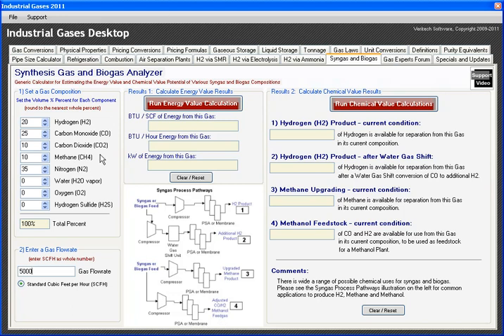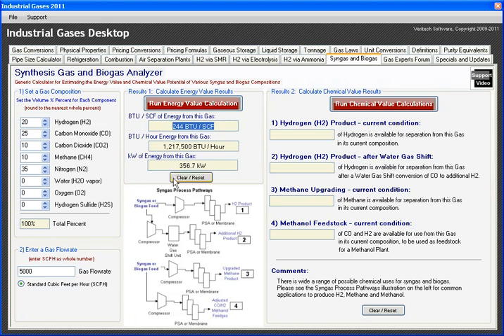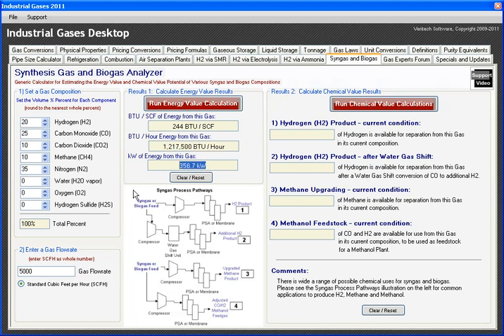That's the basic information needed to run the program. Let's turn to results number one, the energy value calculation. Hit the button and it gives me the energy results of this particular mix, which turns out to be about 244 BTUs per standard cubic foot. The hourly energy available from this gas is about 1.2 million BTUs per hour, which is equivalent to about 356 kilowatts.